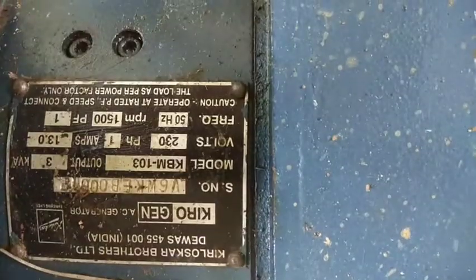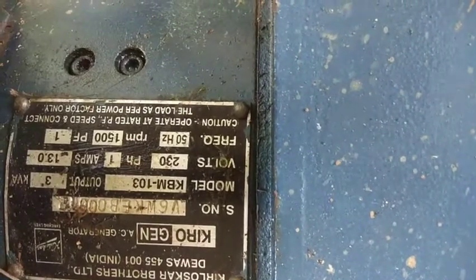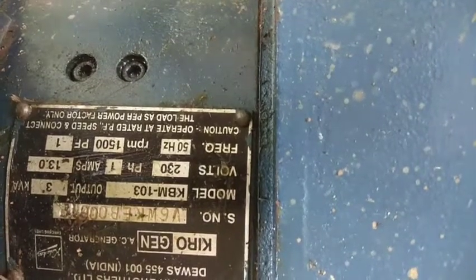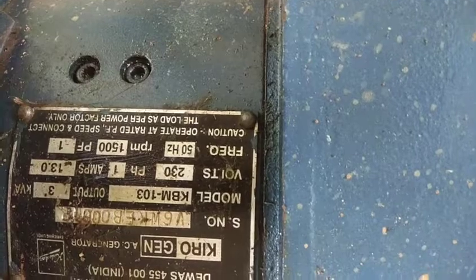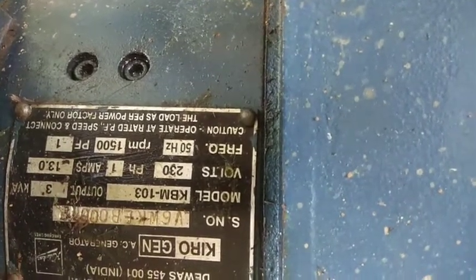So whenever you speak with some experts in this particular alternator field, they say 5 kVA, but basically it is not 5 kilowatt, it is 5 kVA, which stands for 4 kilowatt, because 5 into 0.8 power factor becomes 4 kilowatt.